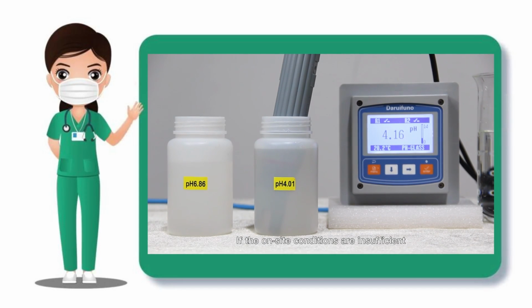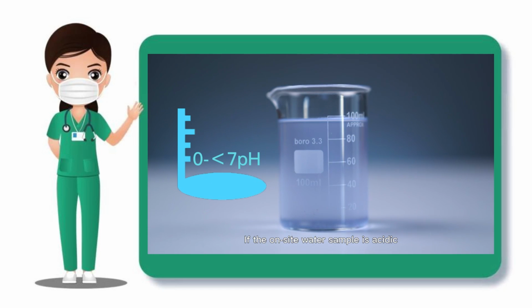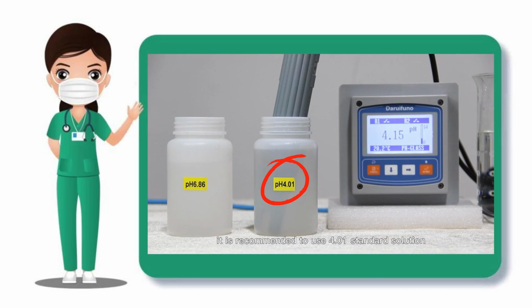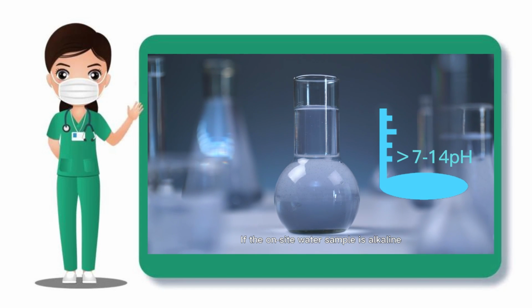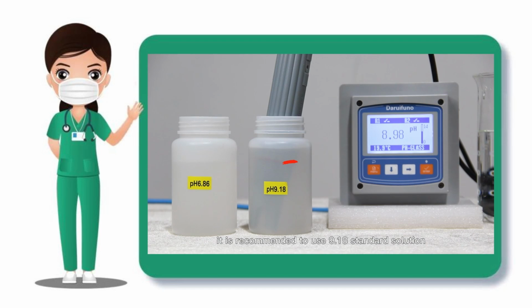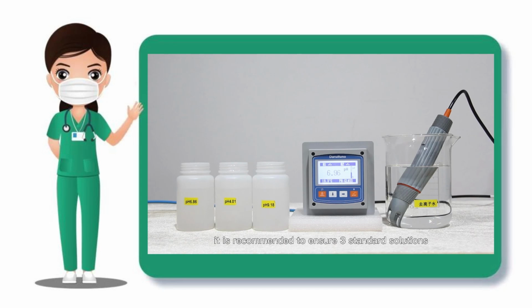If the on-site conditions are insufficient, at least 2 standard solutions are guaranteed, one of which is a 0 standard solution, and the other slope standard solution can be selected according to the on-site water sample. If the on-site water sample is acidic, it is recommended to use 4.01 standard solution. If the on-site water sample is alkaline, it is recommended to use 9.18 standard solution. For neutral water samples, it is recommended to ensure 3 standard solutions.